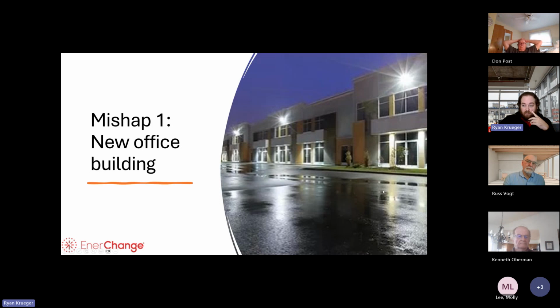And beyond where this photo shows, you're going to have a parking lot that has pole lights that are also throwing light. So you have light bleed from the wall packs that are throwing it to the middle of nowhere that you don't necessarily need because you have pole lights that are illuminating that other side.